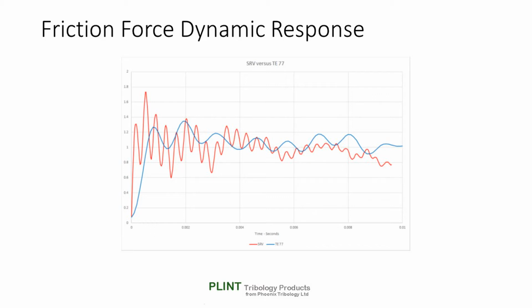The machine has a much smaller and lower mass fixed specimen assembly, consistent with a shorter stroke tribometer, and a much stiffer piezo transducer consistent with a higher load range device. So in both cases, rational engineering choices have been made. It is worth noting that Optimol have sensibly avoided any issues with operating at different frequencies by specifying the same reciprocating frequency, 50 Hz, for all their ASTM test standards.